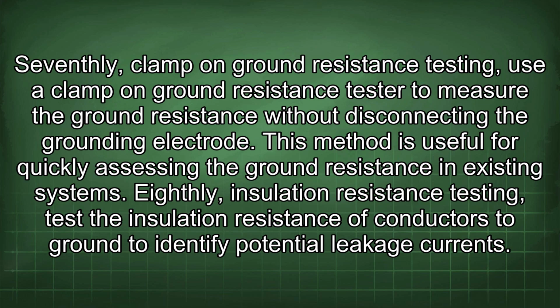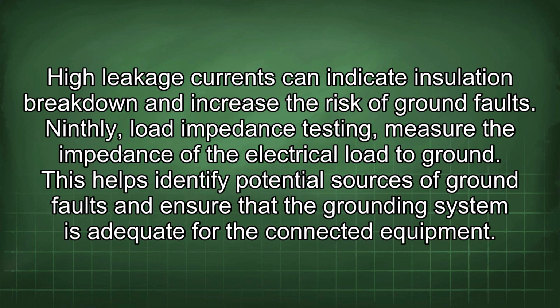Eighthly, insulation resistance testing. Test the insulation resistance of conductors to ground to identify potential leakage currents. High leakage currents can indicate insulation breakdown and increase the risk of ground faults. Ninthly, load impedance testing. Measure the impedance of the electrical load to ground. This helps identify potential sources of ground faults and ensure that the grounding system is adequate for the connected equipment.